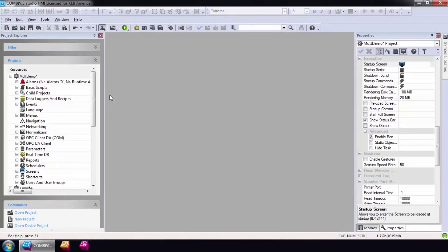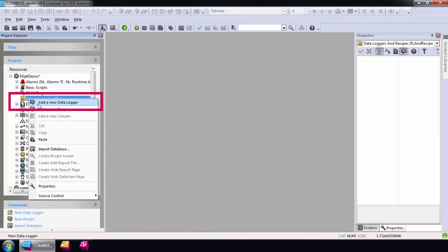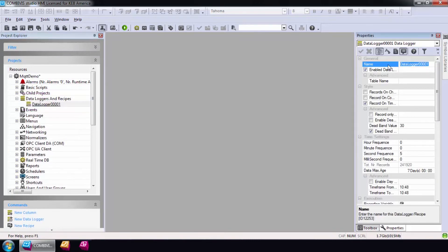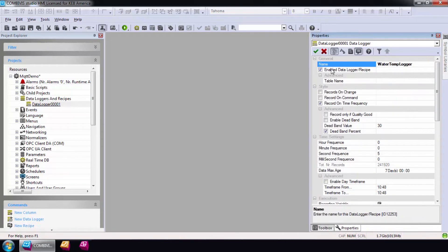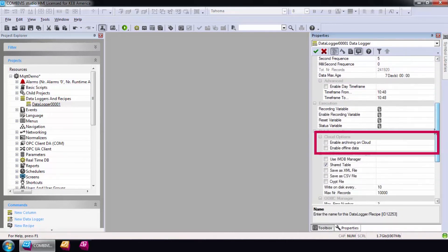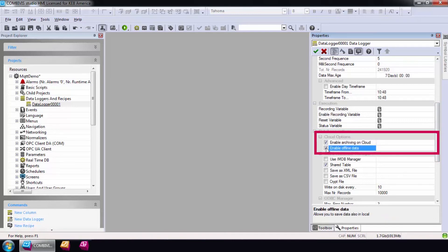To add a data logger, simply right-click on the data logger resource and select Add a New Data Logger. To push data to the cloud, the Enable Archiving on Cloud option must be selected. For environments with an unstable internet connection, it is possible to save data packets to the router memory while an internet connection is unavailable. You can use this feature by selecting the Enable Offline Data option.